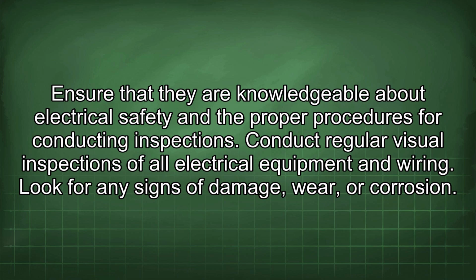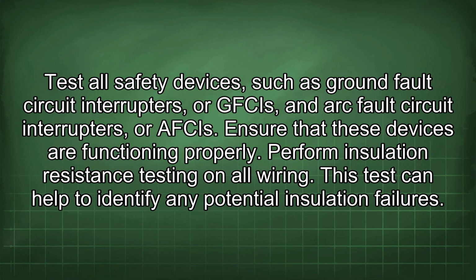Conduct regular visual inspections of all electrical equipment and wiring. Look for any signs of damage, wear, or corrosion. Test all safety devices, such as ground fault circuit interrupters (GFCIs) and arc fault circuit interrupters, ensuring these devices are functioning properly. Perform insulation resistance testing on all wiring, which can help identify any potential insulation failures.